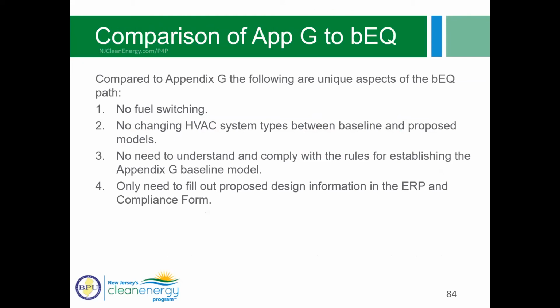Lastly, we'll just do a comparison of Appendix G to bEQ. Like I talked about before, no fuel switching. Next, no changing HVAC system types between the baseline and proposed. With Appendix G, you might have PTAC in the baseline, or a multi-zone variable air volume system with gas-fired boilers, and then your proposed is VRF. So you've got to do a save as on your model and create a whole new one, and it might add a lot of extra work.